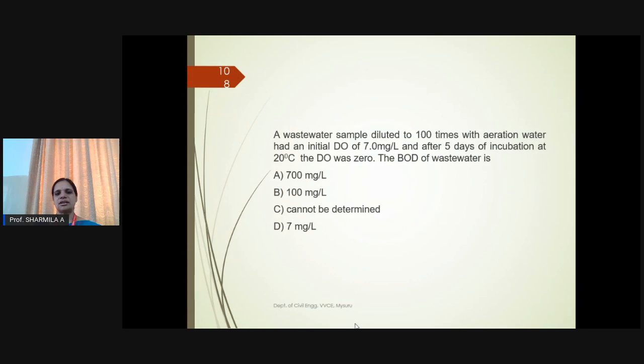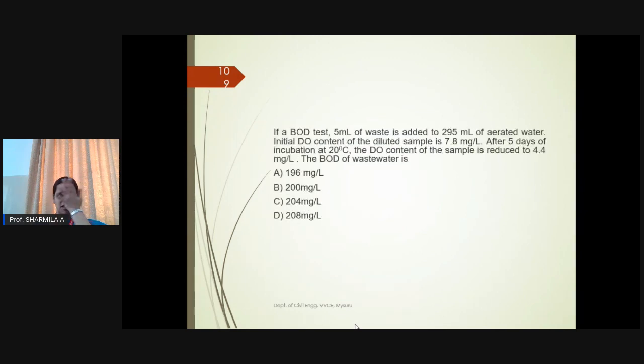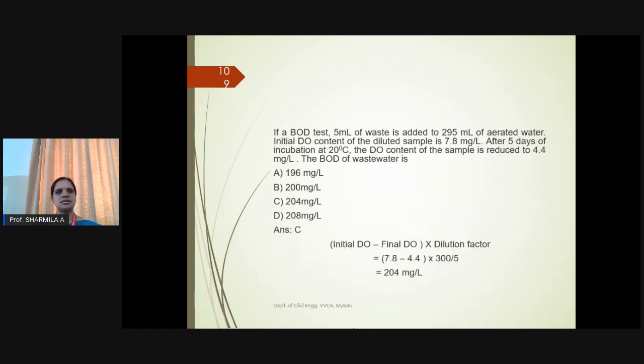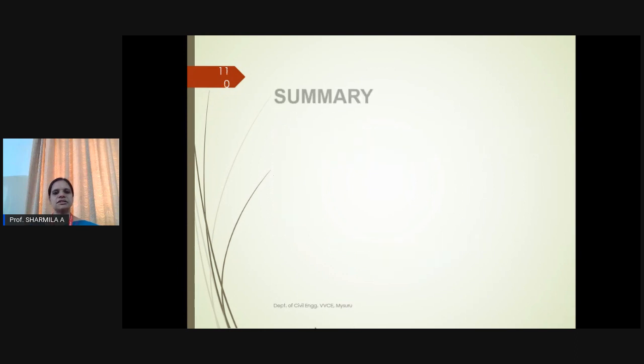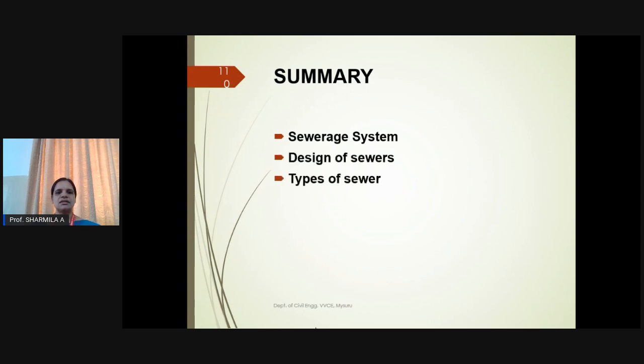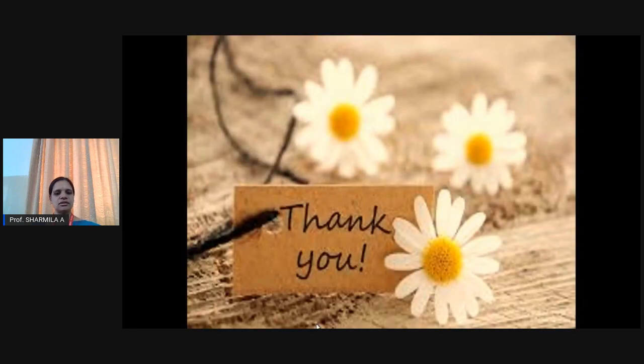If a wastewater sample is diluted 100 times and the initial DO is 7 mg/L and after 5 days incubation it is 0 — this cannot be determined as the DO has gone to zero, meaning all oxygen was depleted before the test ended. BOD test problem: 5 mL of waste is added to 295 mL of diluted water; initial DO of diluted sample is 7.8 mg/L; after 5 days at 20°C, DO is reduced to 4.4 mg/L. BOD = (initial DO − final DO) × dilution factor = (7.8 − 4.4) × (300/5) = 204 mg/L. Summary: We learned about sewerage systems, design of sewers, types and shapes of sewers, characteristics of wastewater, and BOD calculations. Thank you, we'll meet in the next session.